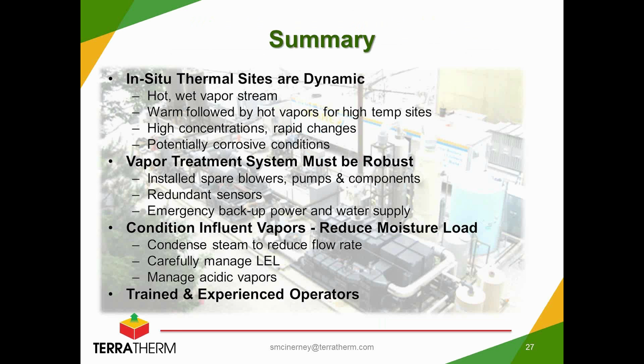So we're reaching the end of the presentation. Just want a couple of wrap-up points here. Vapor treatment applications for thermal sites can be very dynamic situations. We've got warm, wet vapors at times. We've got very hot vapors that are bone dry, and a combination of the two when we've got high temperature targets for thermal desorption. Highly impacted sites translate to highly contaminated or concentrated vapor streams impacting our vapor operations. And those changes in concentrations and loadings can happen very, very fast. And as I discussed, there are potential corrosive conditions that need to be managed.